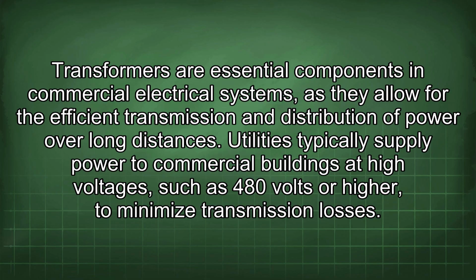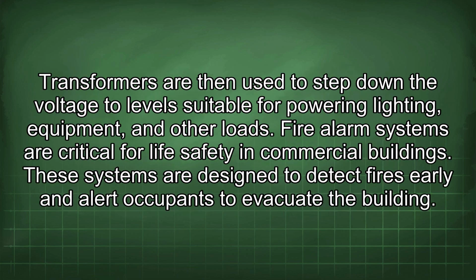Transformers are essential components in commercial electrical systems, as they allow for the efficient transmission and distribution of power over long distances. Utilities typically supply power to commercial buildings at high voltages, such as 480 volts or higher, to minimize transmission losses. Transformers are then used to step down the voltage to levels suitable for powering lighting, equipment and other loads.